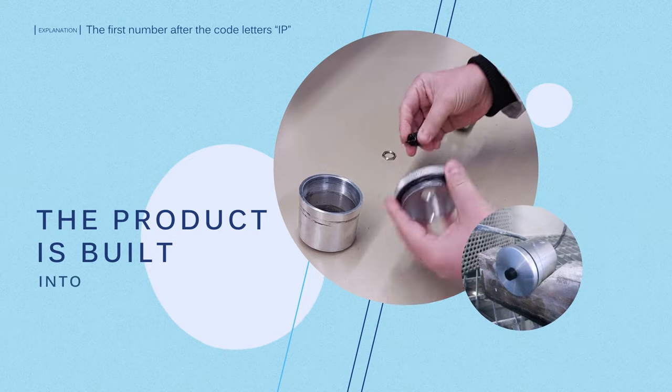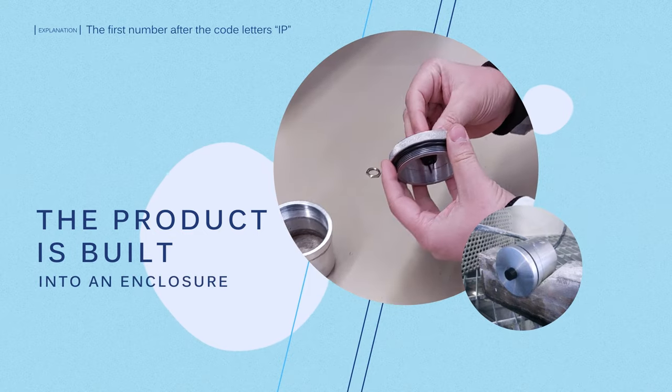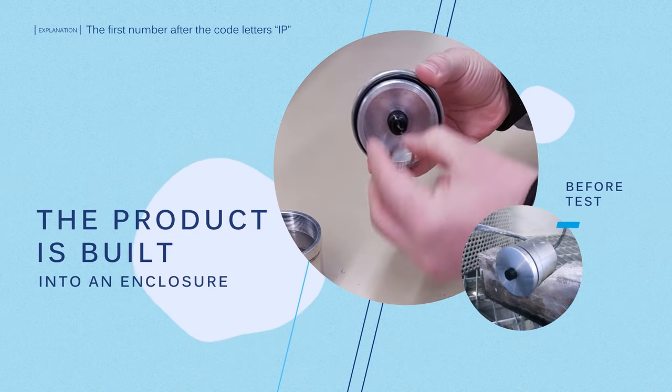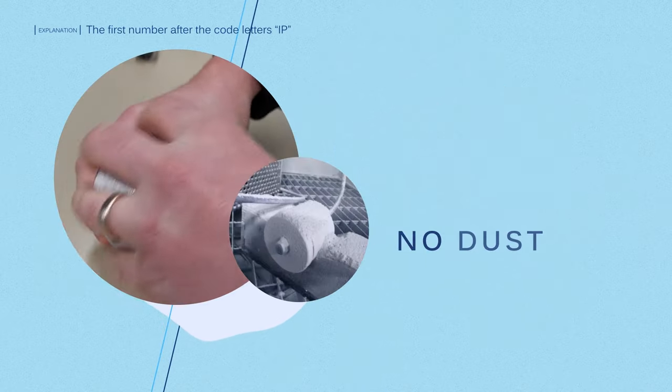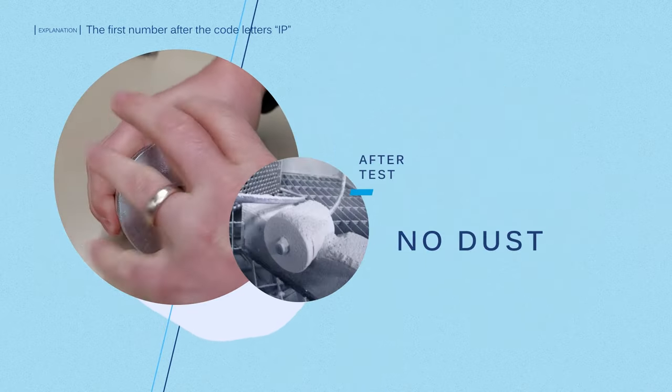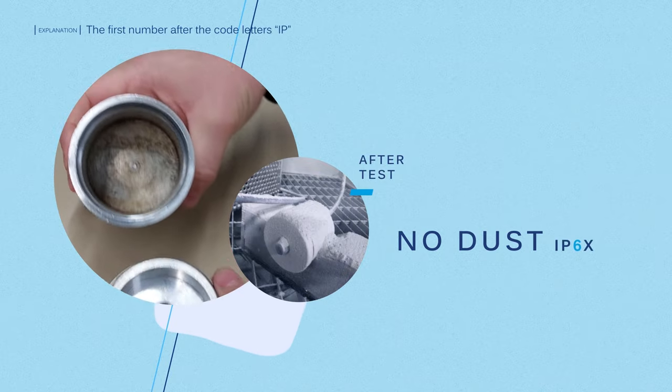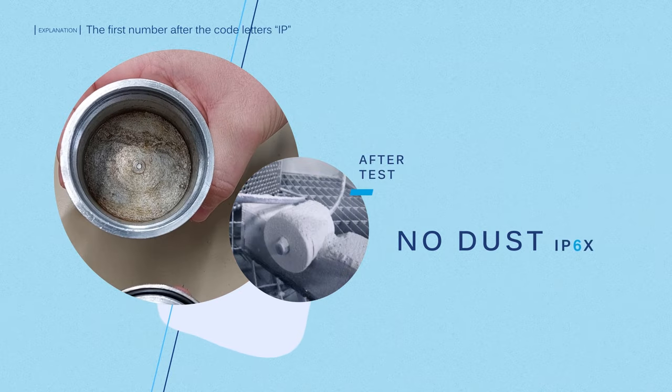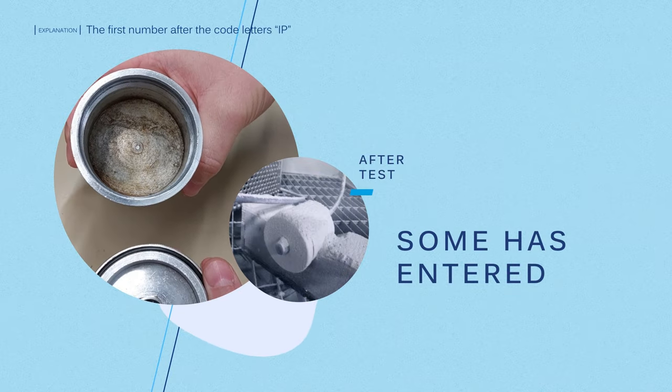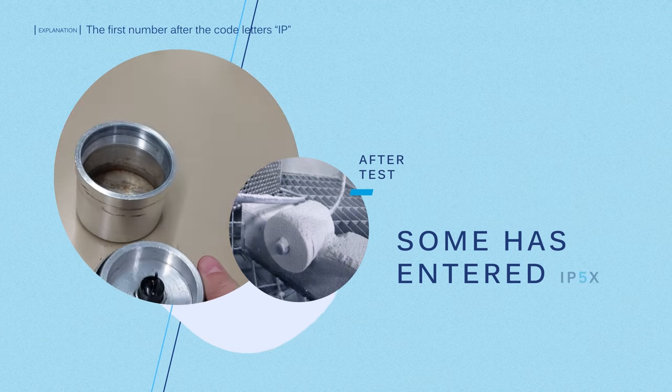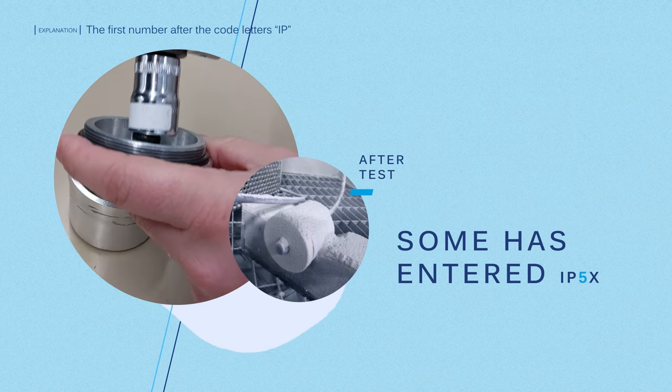The product is built into an enclosure and placed in a dust chamber for 8 hours. If no dust has entered the enclosure, it is IP6X. If some has entered but it is not harmful, it is IP5X.